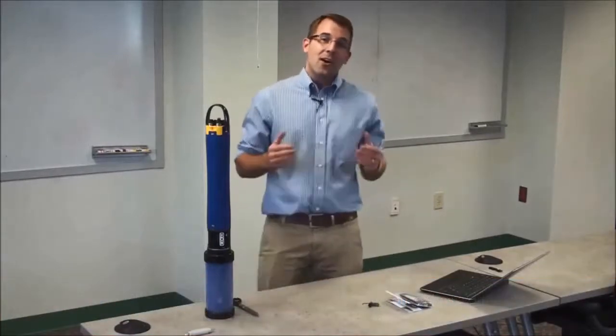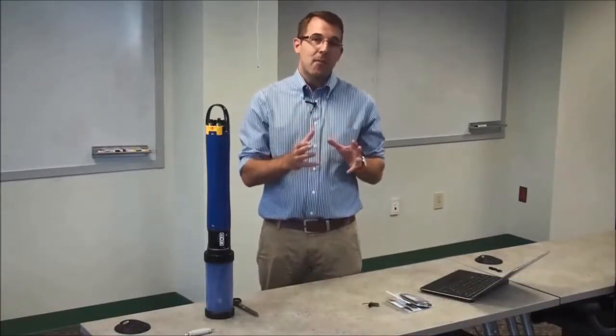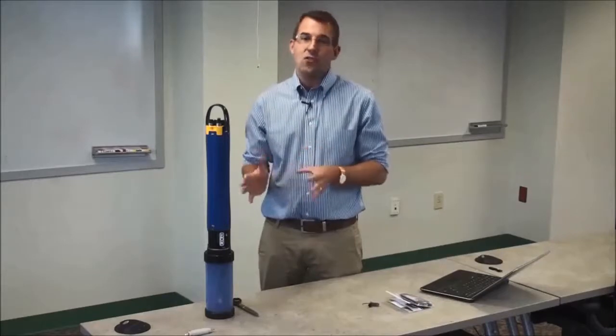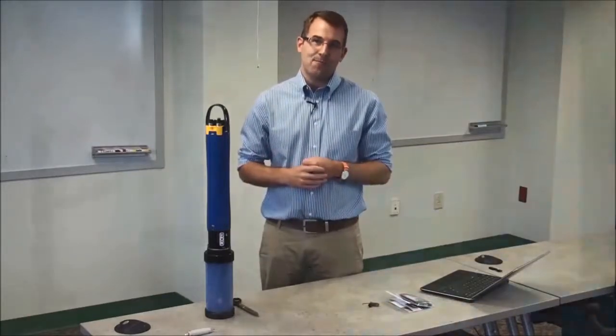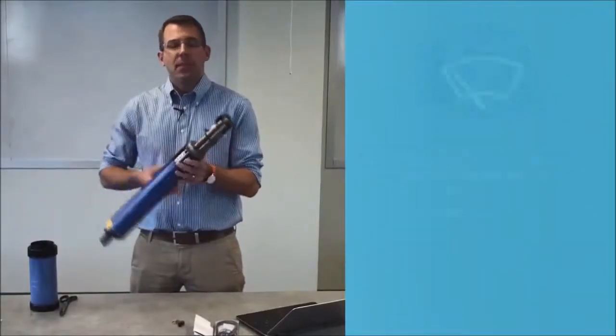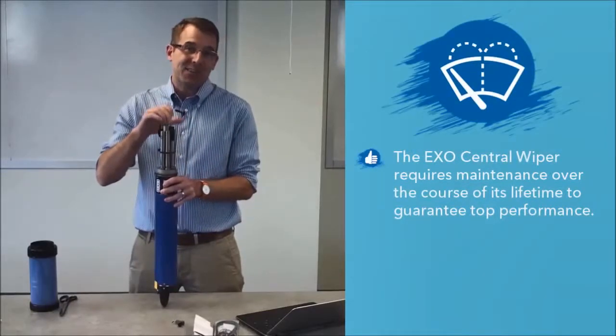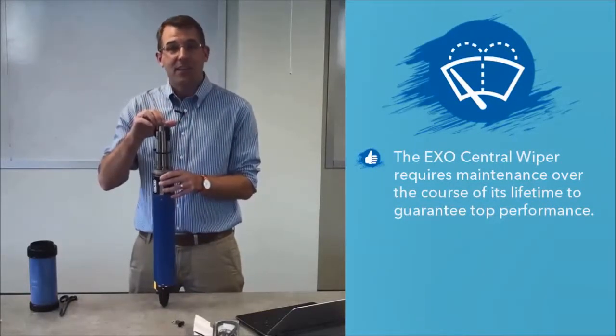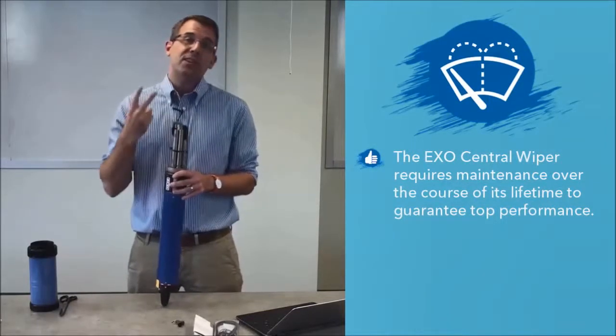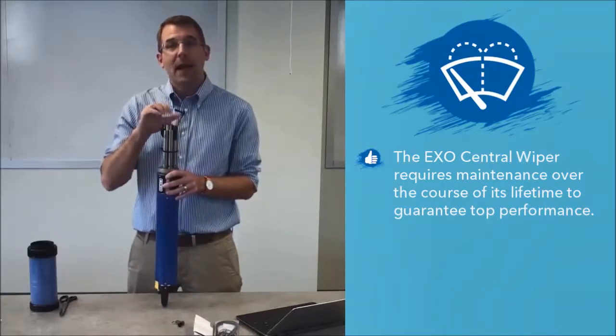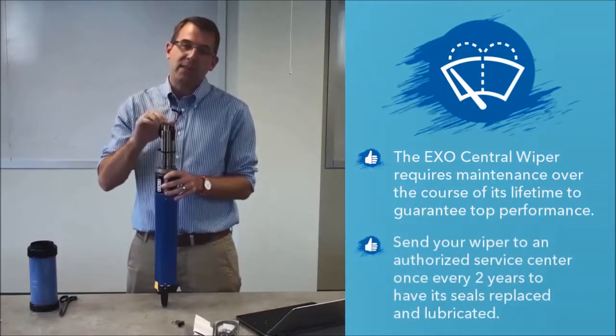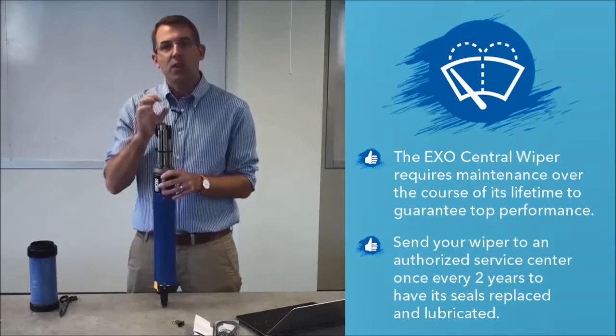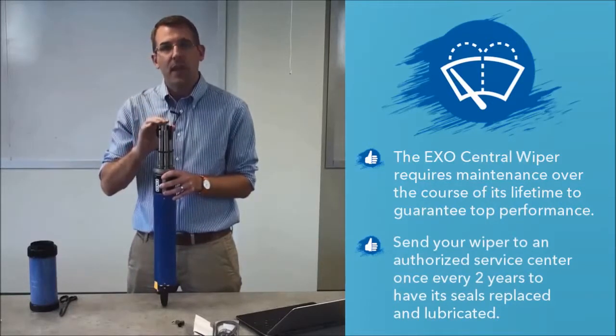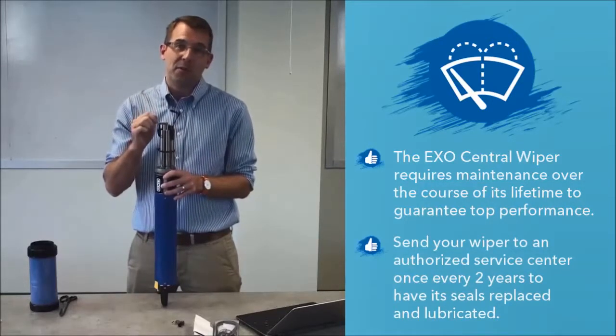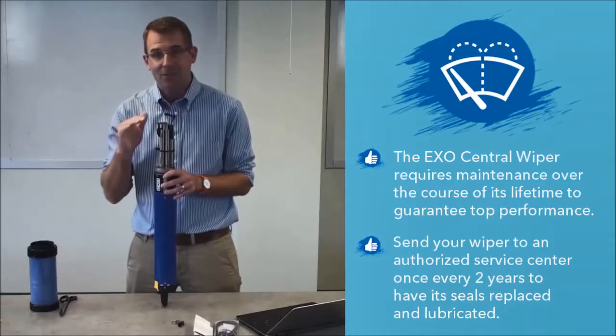Let's wrap up now by talking about some of the key things you need to keep in mind to get the best performance out of your new wiped conductivity cell. The first tip is to be sure to properly maintain your central wiper, as it's the heart of the cleaning system on your EXO. Every 2 years, you want to send your wiper back to the factory where they can replace the wiper seals and re-lubricate the entire system. That's going to give you the best possible performance of your wiper in any application.